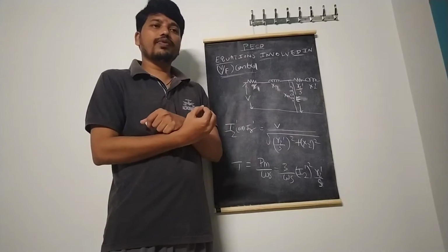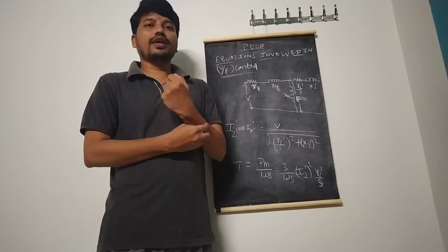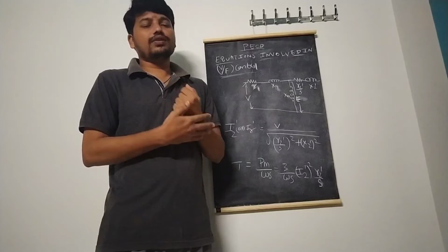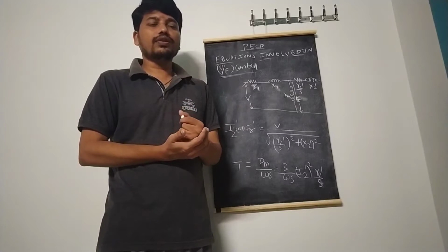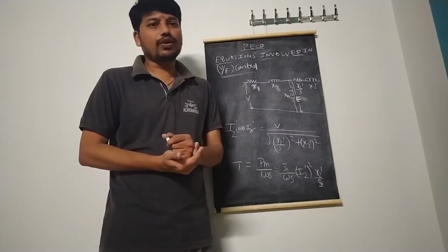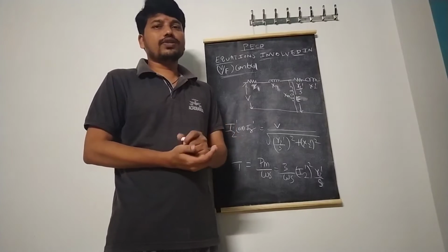In case of only variable frequency, that means only frequency control, what is the problem? The flux becomes less than the required flux, or it becomes more than the required flux. That means the flux is less or the flux is more. If the flux is more, that is called saturation condition. If the flux is less, you will not develop sufficient torque for the motor.